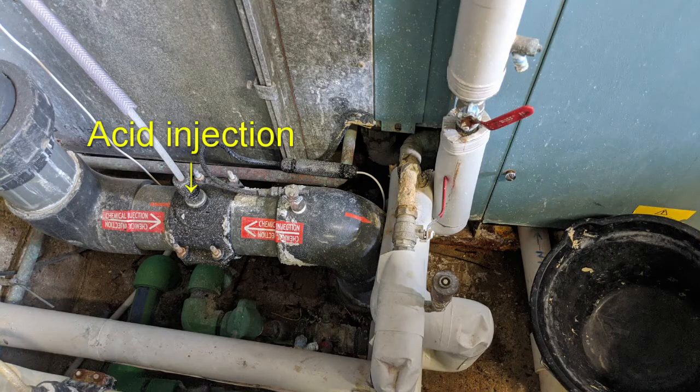And then somewhere around this point, you'll probably come across another chemical being injected into the system. This is likely to be the pH correctant. In the majority of plant rooms in the UK, the disinfectants are highly alkaline, so there's always a necessity to add in some sort of acidic substance to bring the pH back down. This is usually the final thing to be injected into the system because it's acidic.